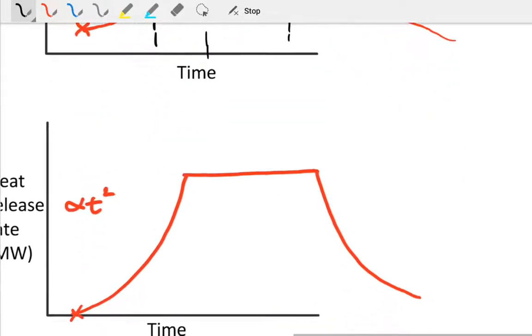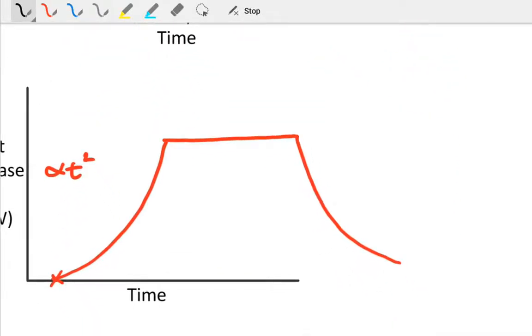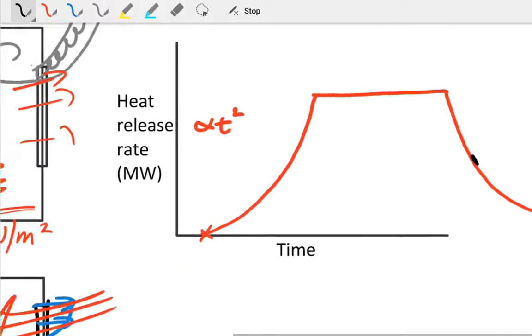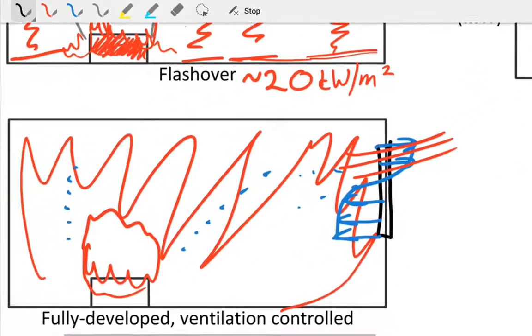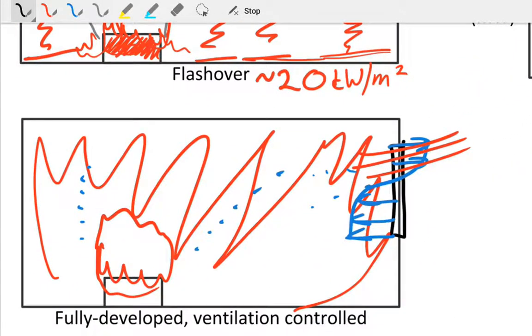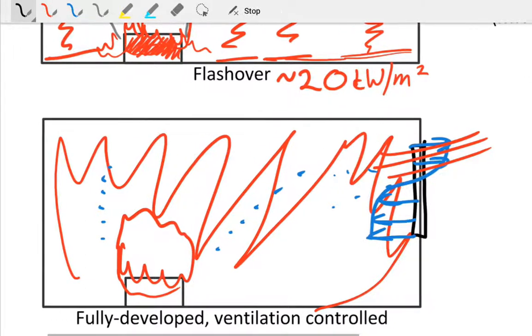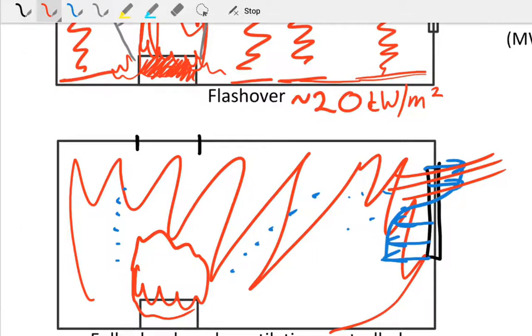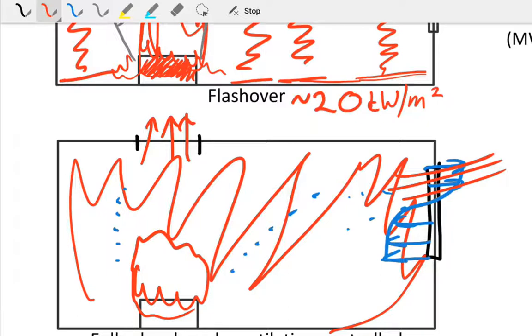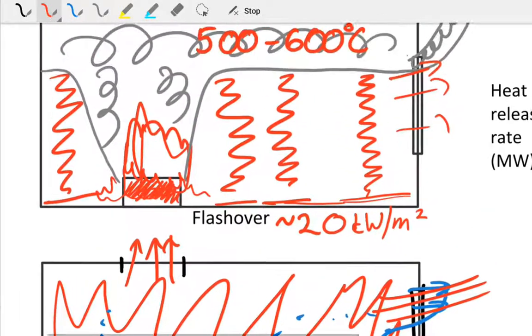That's the same thing as the decay phase there. That could be influenced—all this behavior could be influenced by various different items. For instance, in the room if we have vents, this allows hot gases to escape. That'll delay the time to flashover and maybe even drop the temperature in the room as hot gases can escape and it doesn't build up as much. If you're in a very big room, coming to our flashover, if you've got a tall atrium and you've got a large distance there, you may not have enough heat to actually cause flashover.